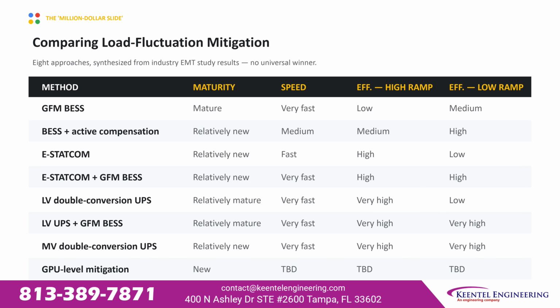8 mitigation approaches, synthesized from industry EMT study results, and there's no universal winner. Grid-forming battery storage is mature and very fast, but efficiency drops at high ramp rates. Battery storage paired with active compensation is newer and moderate in speed, but performs well across both high and low ramp rates. An eStatCom alone is fast and highly efficient at high ramp rates, but weaker at low ramp rates.